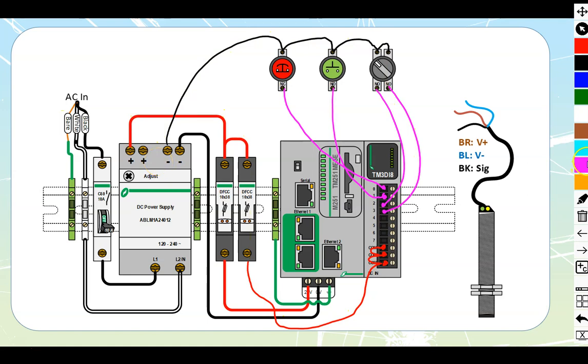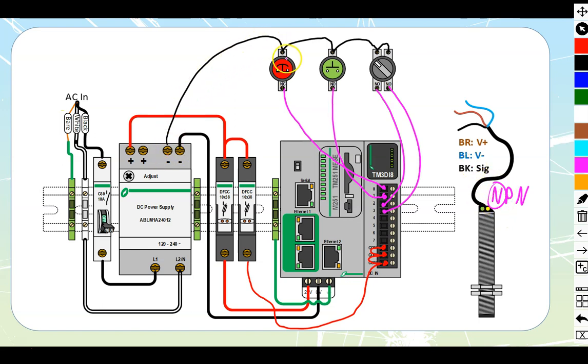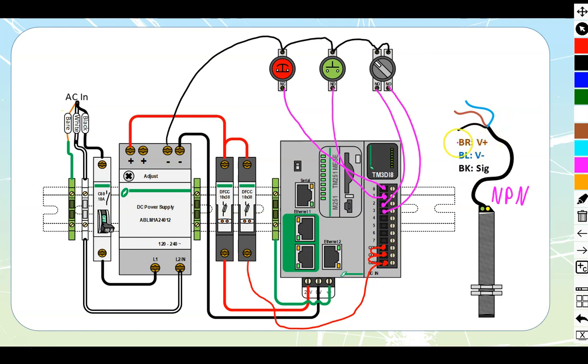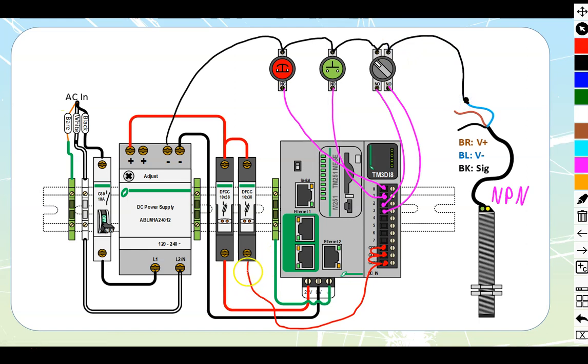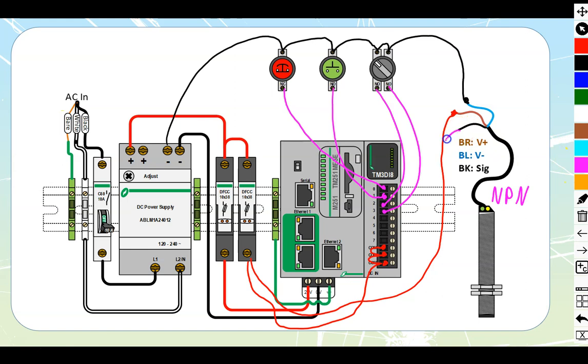All right. Last component that we have to hook in over here is going to be this sensor that we have over here. Sensors are going to fall under one of two categories. We are going to have PNP or NPN. What we would want if we are doing sourcing would be NPN. The first letter tells you what this thing is going to be switching out. It's going to be switching out a negative, which if we take a look, that's what we're switching to our PLC and everything else. We want to match that. PNP would not give us a voltage differential. These three-wire sensors are commonly going to be coded with brown, blue, and black. Brown is going to be the positive value of voltage. Blue is going to be the negative. And black is going to be the signal back. So we'll just finish up those connections. We'll take our negative to our blue. We will take our positive, we'll come off of this same terminal that we just had that one at over there. We'll run that all the way up to here. Make a connection onto there. And then this last one over here is just going to be now my signal from there back into my PLC. And there we've got a proper three-wire sensor connected in as well.